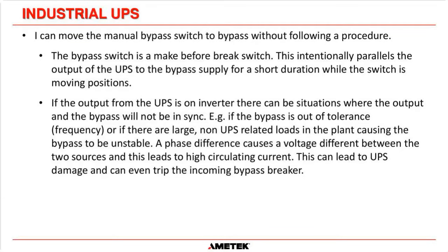I can move the manual bypass switch to the bypass position without following a procedure. Please do not do this. The bypass switch is a make before break switch, and that means it intentionally parallels the output of the UPS to the bypass supply for a short duration while the switch is moving positions.